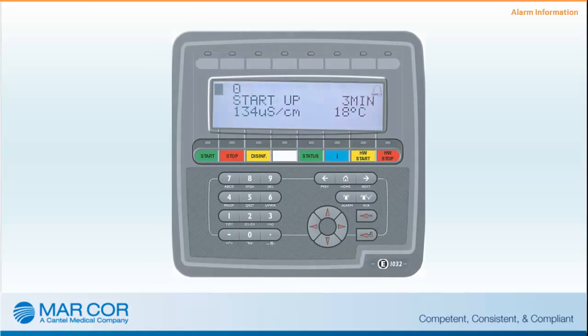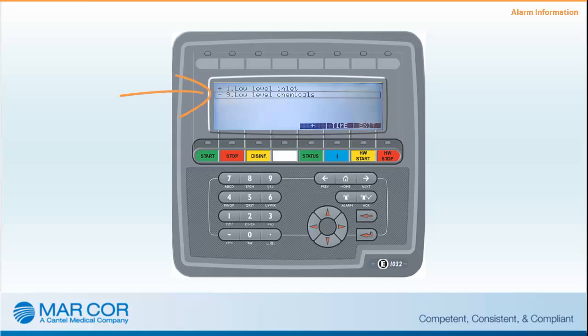When an alarm occurs, an alarm bell symbol will be displayed in the upper right corner of the display screen. To determine the cause of the alarm, press the Alarm button. The alarm list will display the last 32 alarms that have occurred, with the most recent alarm at the top. Four attempts are automatically made to self-clear alarms by the CWP prior to alerting the operator. The current alarm will have an asterisk symbol in front of it. If the cause of the alarm has been corrected before acknowledgement, the asterisk symbol will change to a minus symbol.